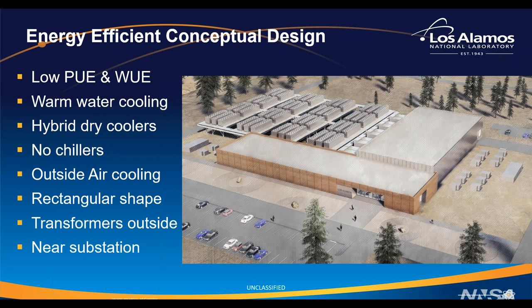The supercomputer that goes into this building uses warm water cooling, and it uses hybrid dry coolers to reduce the temperature, to reject the heat to the outside. It does not have any chillers, so everything's done with the hybrid dry coolers.